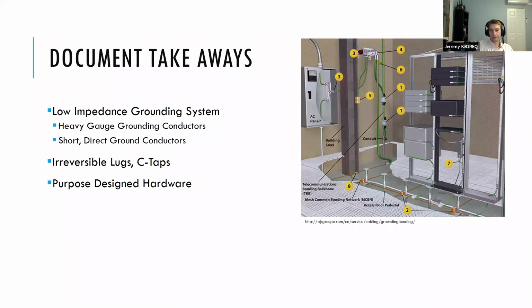Those are all very long technical manuals that I think are definitely worth the read. You get a lot out of them, but there's no bullet points, right? You got to really dig into them. So some of the bullet points that you might get out of going through all of them is the importance of a low impedance grounding system. This provides the best protection, and it's constantly repeated in all of those documents. They talk about, it must be a low impedance grounding system.